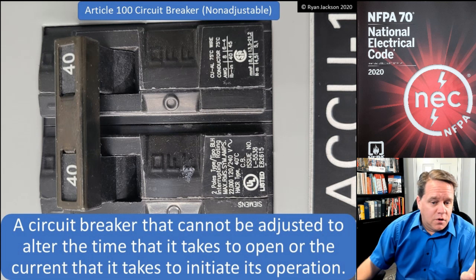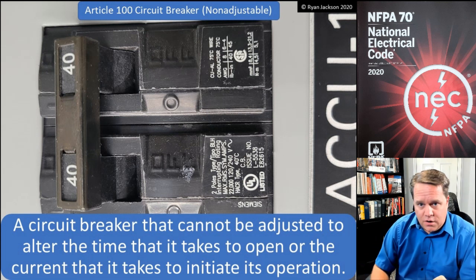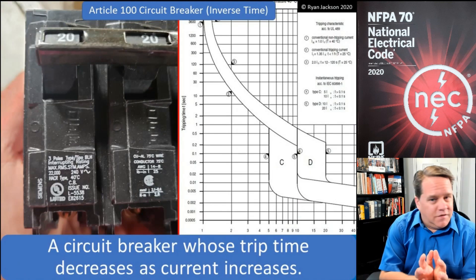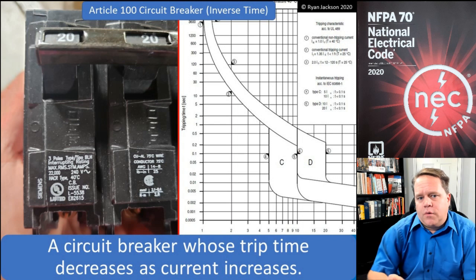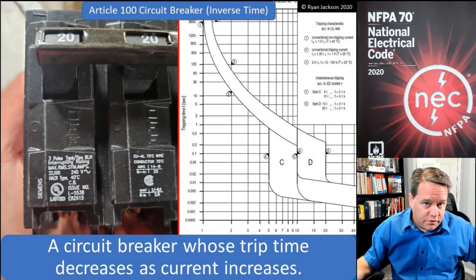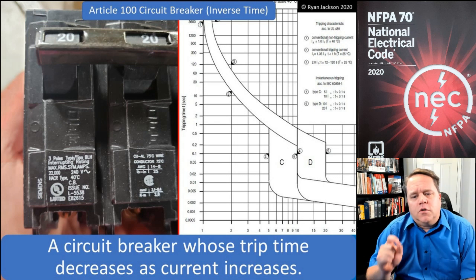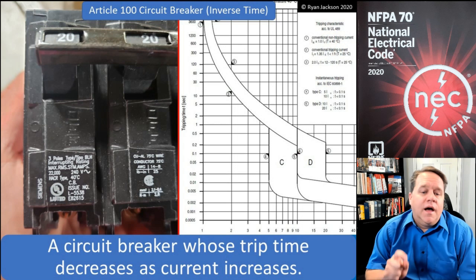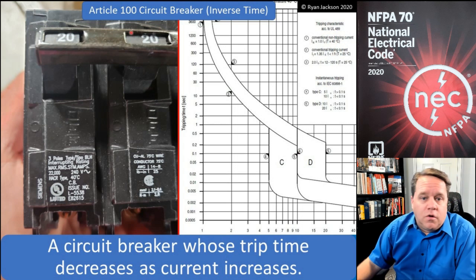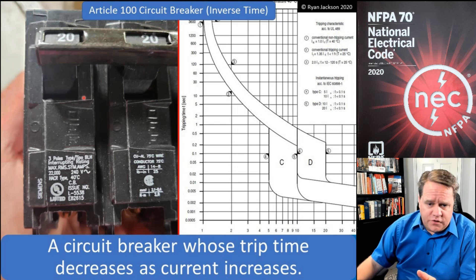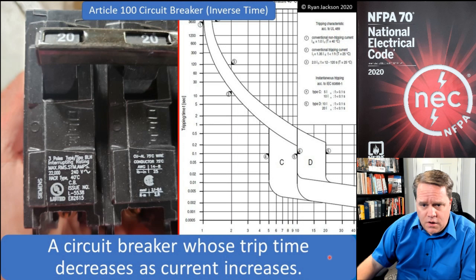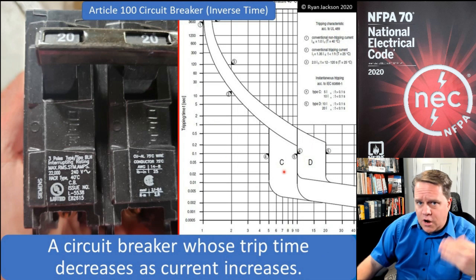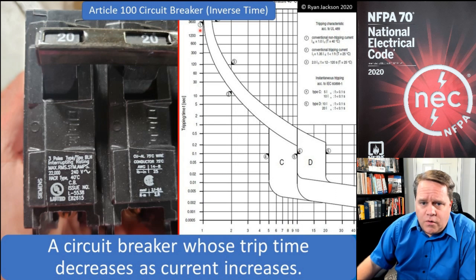A non-adjustable breaker — we cannot adjust the time it takes to open or the current that initiates that operation. The definition of an inverse time circuit breaker: it's a circuit breaker whose trip time decreases as the current increases. A regular molded case circuit breaker works on this principle. On the right we have an inverse time characteristic curve showing how fast it will open based on how much current it receives — time going up to down, current going left to right.